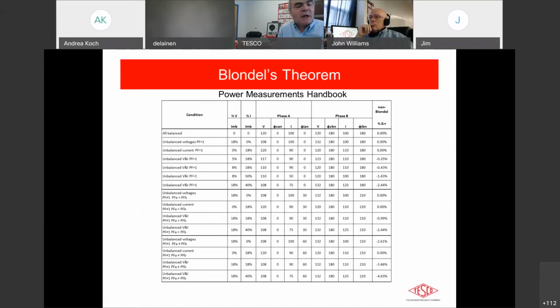This is out of the power measurement handbook that Dr. Hardy put together. And what it demonstrates to you is that if you've got a perfectly balanced load, okay, with a power factor of 1, your 2S meter, that 5S meter that we had, is actually going to be perfect. You're going to be able to use a non-Blondel solution, and you're going to get the right results. But as soon as you start unbalancing your load, as soon as you start moving away from a power factor of 1, you will start to create errors. Even though all the equipment is working correctly, you've wired up a bad solution. How bad does that solution get? If you look over in the far right column, you can see that it starts getting over 2%, 3%, 4% as it starts getting really bad.